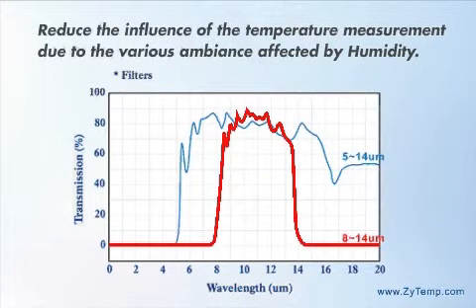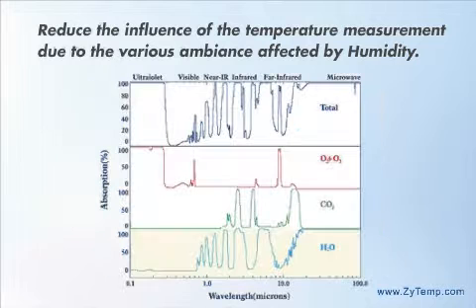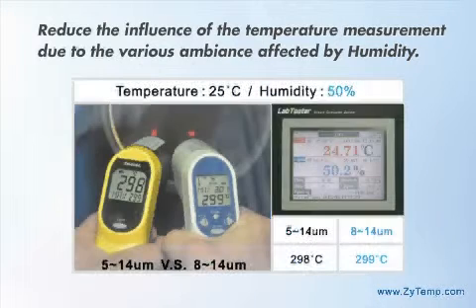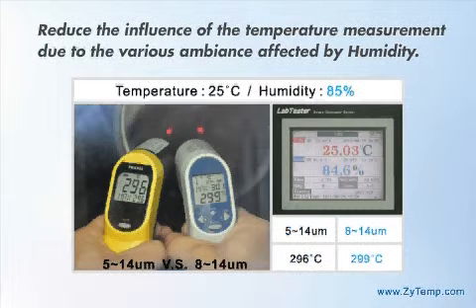Water has several absorption bands in the infrared and even some absorption well into the microwave region. Therefore, we choose an 8 to 14 micrometer thermopile sensor that can dramatically reduce interference in temperature measurement due to humidity in the environment. The 8 to 14 micrometer thermopile sensor is more expensive than the 5 to 14 micrometer because of the extra coating layer for the filter.